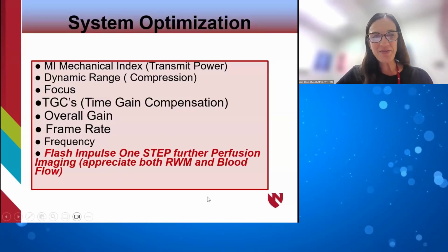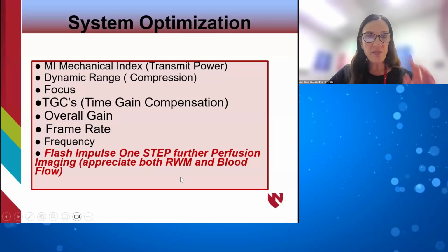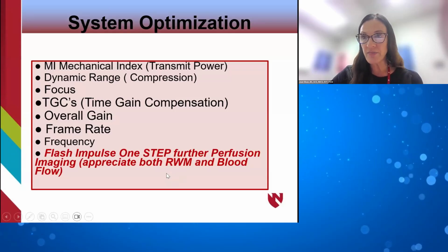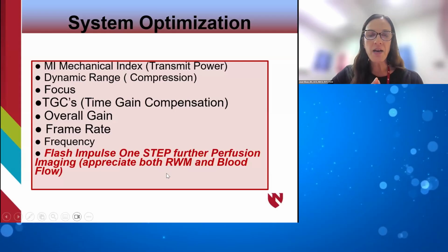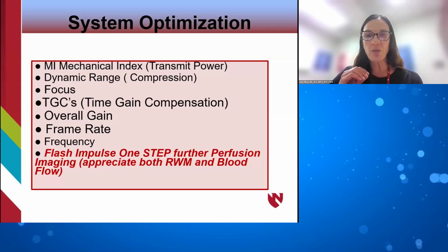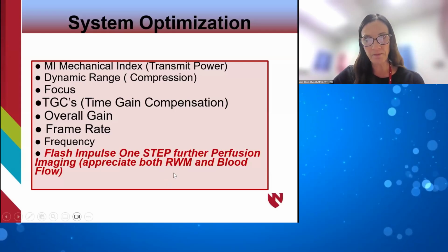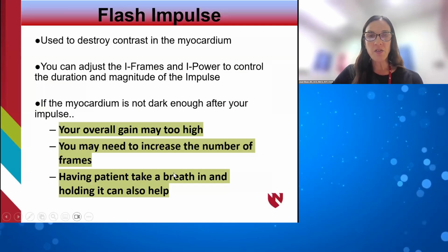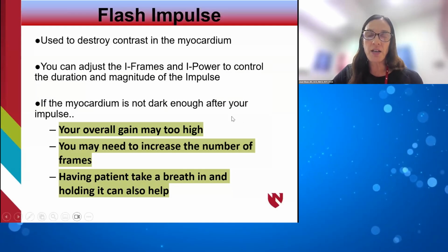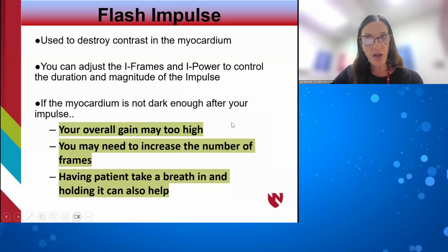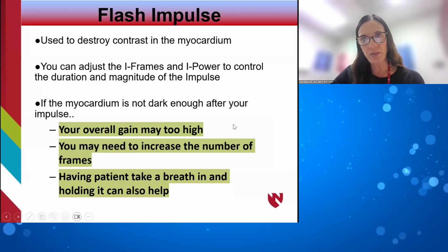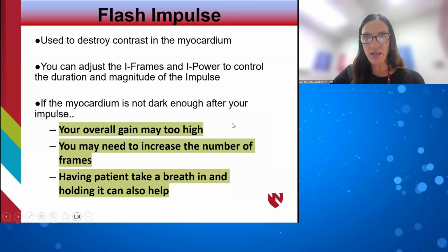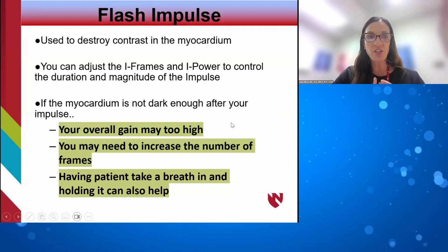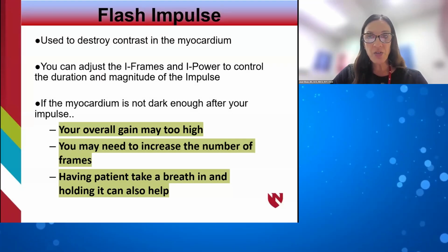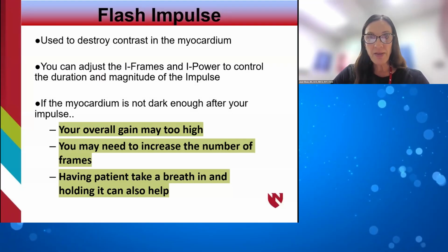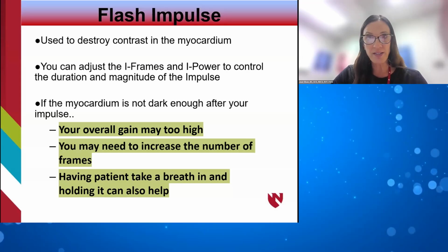One last thing is the flash impulse. We can take it one step further, and this would be for perfusion imaging. Most of the machines now are set up for that. With this perfusion imaging, this low MI imaging, you can appreciate both regional wall motion and blood flow to the heart. The flash impulse is used to destroy contrast in the myocardium. You can adjust the flash frames and the flash power to control the duration and magnitude of the impulse. If the myocardium is not dark enough after your impulse, your overall gain may be too high, like we talked about. You may need to increase the number of frames, and having the patient take a deep breath in and hold it can also help with contrast images.